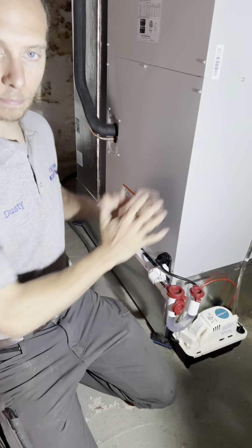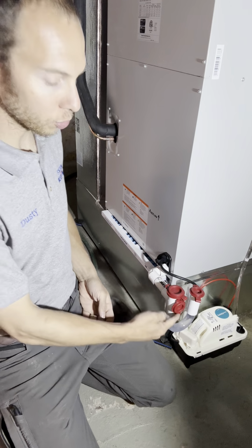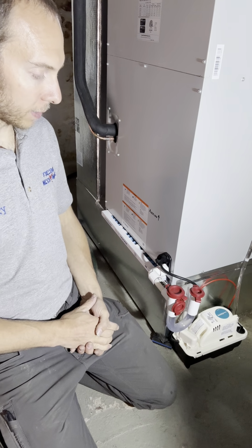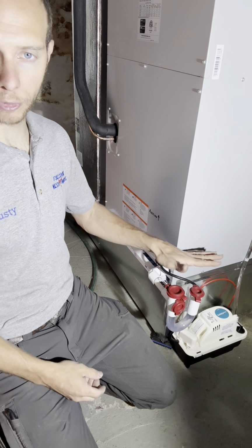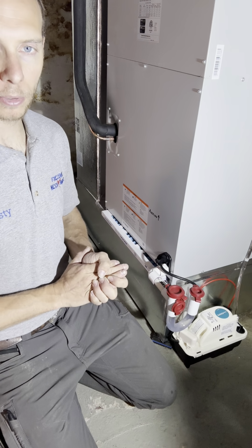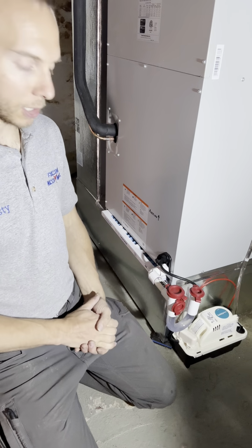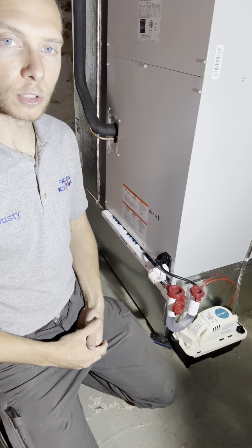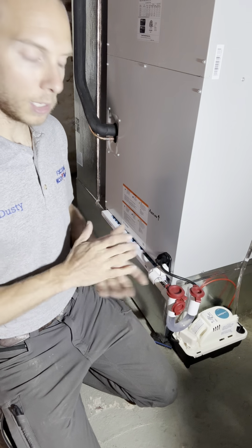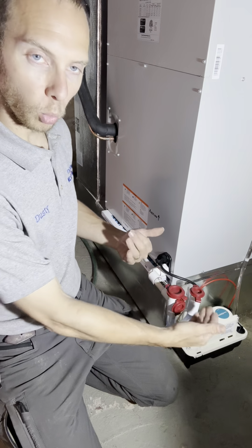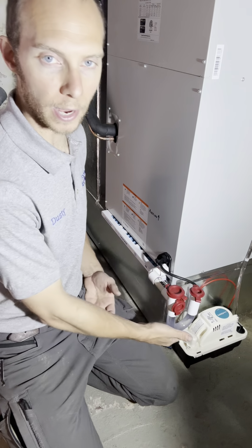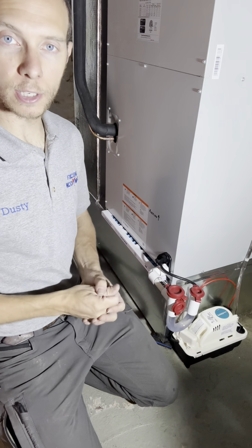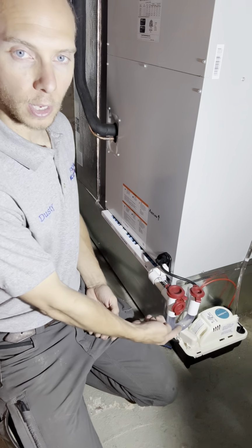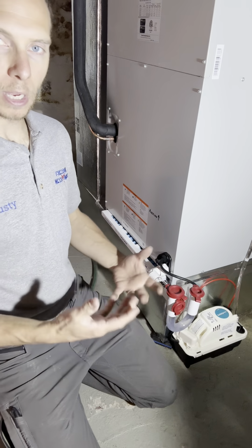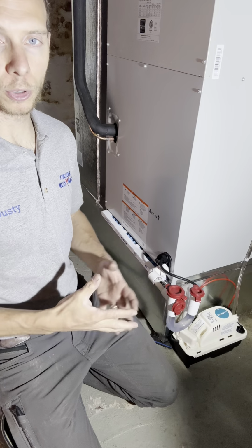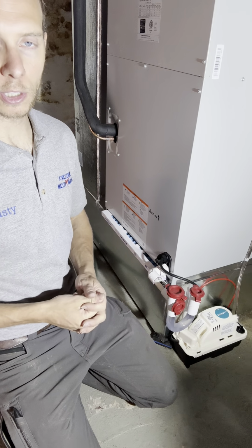This system, as an air conditioning system, needs to have a trap. So this is a trap, and that's something that we pay attention to. I have a small vent hole here, which is very important to allow this system to drain properly with the condensate pump, so we got to pay attention to that. Something as a homeowner that you need to know, though, is each season that passes, the heating system may pull enough air through this in the winter to dry it out. So when you switch to air conditioning, make sure there's a little bit of water in here, at least up above the bottom bubble there, to make sure that this is going to drain properly for you, the first cycle of the air conditioning season is very important.